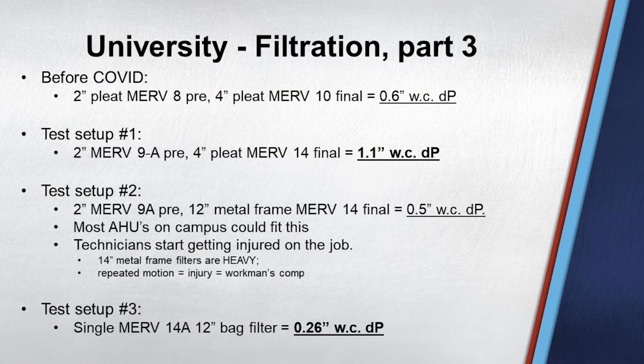They had an empty campus in the beginning of this, and they had a lot of equipment. So they looked at their before COVID standard, 2-inch MERV 8s with 4-inch MERV 10s, and a clean pressure drop of 0.6. So they said, let's do a couple different setups. 2-inch MERV 9 pre, 4-inch MERV 14 final. That's 1.1 inches clean. That's a no-go. Test setup number 2 was 2-inch MERV 9, 12-inch metal frame MERV 14 final. That's a 1/2-inch pressure drop.